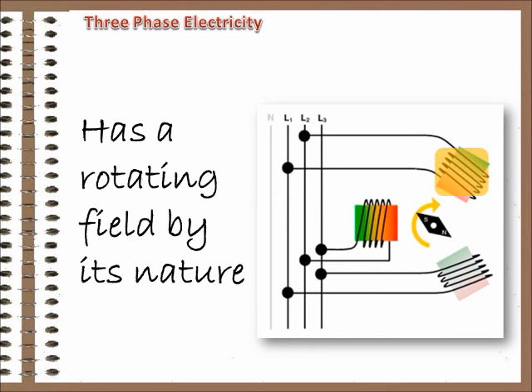Motors that operate on three phases get that rotating field as part of the supply. The phases arrive 120 degrees apart from each other, so they rotate from the get-go. No modification required. This is the reason we have three phases instead of four, five, or more. Three is the minimum number to give a rotating field for motor starting. More wouldn't help and would cost more.